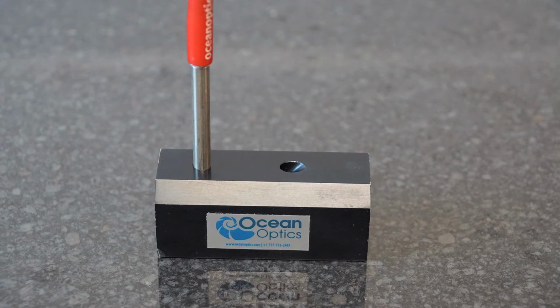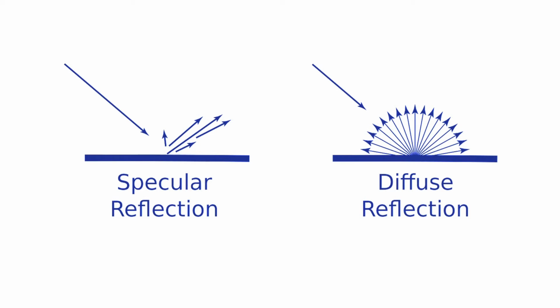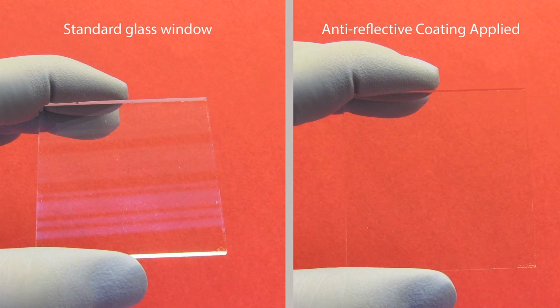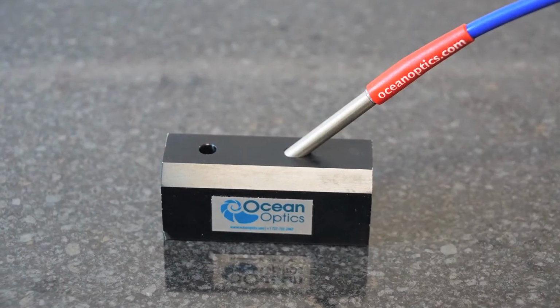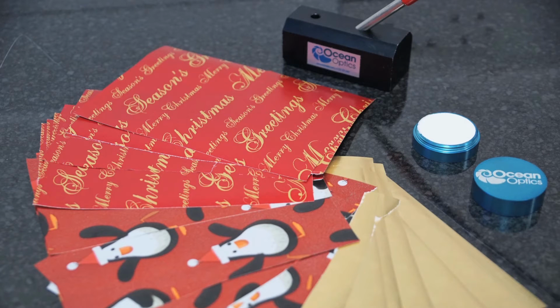This can either be placed at 45 degrees to the sample or at 90. If placed at 90 degrees, you will receive more light into your spectrometer, which will include plenty of specular reflection. This can be useful when you intend to measure specular reflection, or when there are very low levels of reflection. The colour we see is mostly caused by diffuse reflection, so when measuring colour, it is best to have the reflection probe at 45 degrees. In this particular application, the wrapping paper provides a lot of specular reflection, so it is even more important to remove the specular reflection in order to get an accurate measurement.